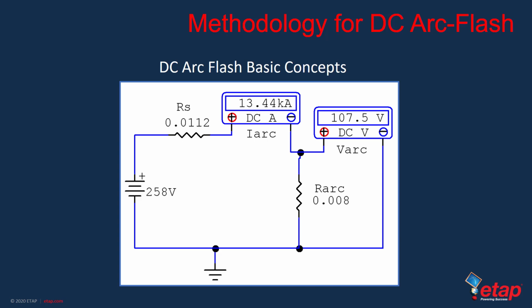The dynamics of the arc as it ignites and extinguishes are hard to capture and thus are typically neglected for most arc flash models. In fact, in the development of the new IEEE 1584 AC arc flash model, we decided to neglect the arc ignition and extinction phases. So, going back to DC arc flash, the task at hand is to find a relationship that defines the arc resistance once the arc stabilizes, or basically after it has ignited and has become an actual arc event.